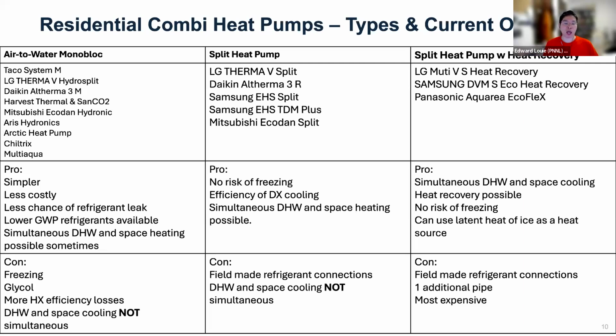Other systems that attempt to do simultaneous heating and cooling work like this: the outdoor unit will switch. It'll work on recharging the domestic hot water tank, and then when it's done, it'll switch back to cooling. And if you have two buffer tanks, then you can, at least on the experience side, have what seems like simultaneous heating and cooling, but the outdoor unit is not actually doing simultaneous heating and cooling.